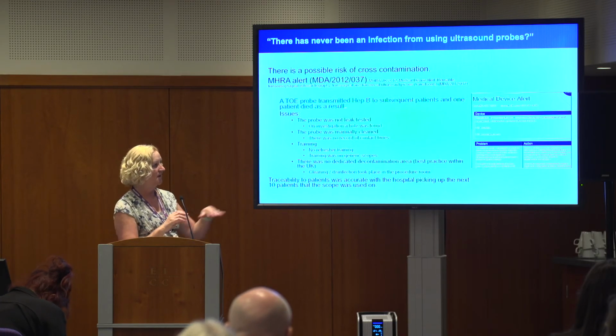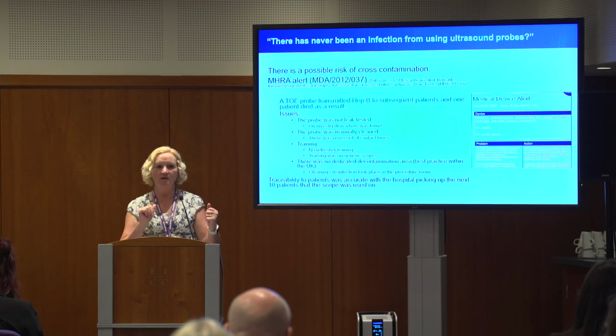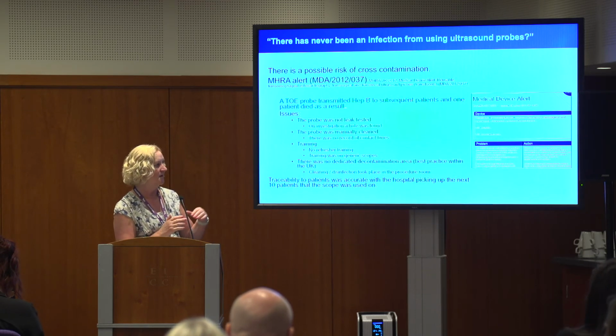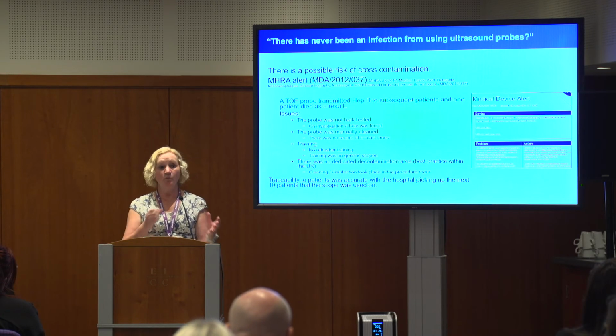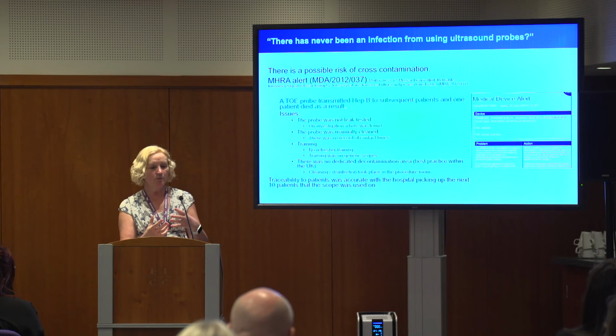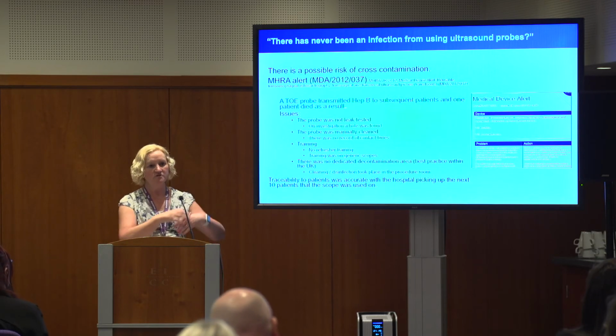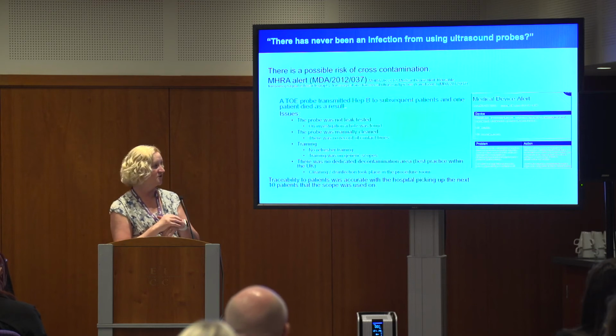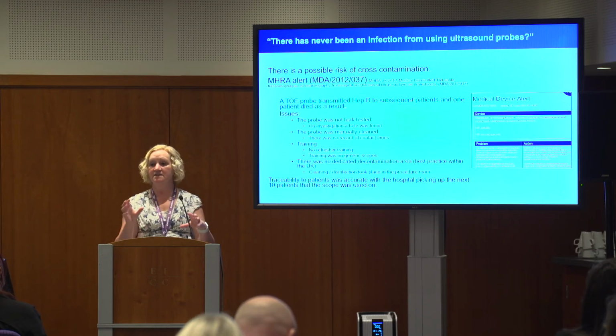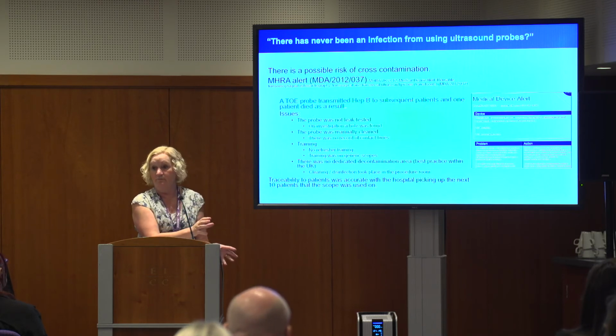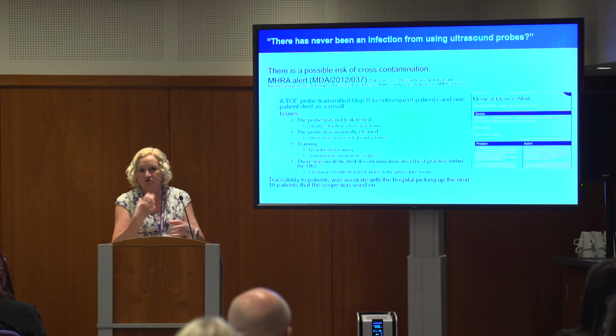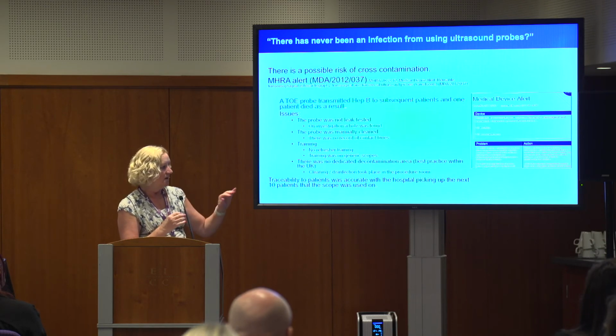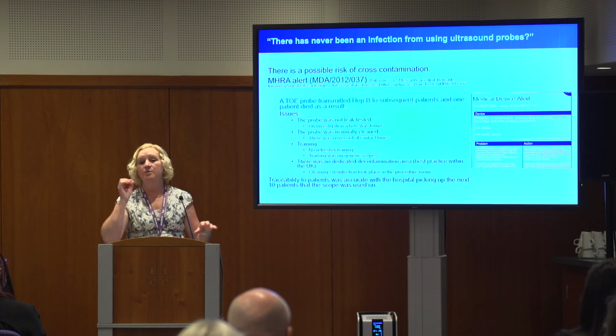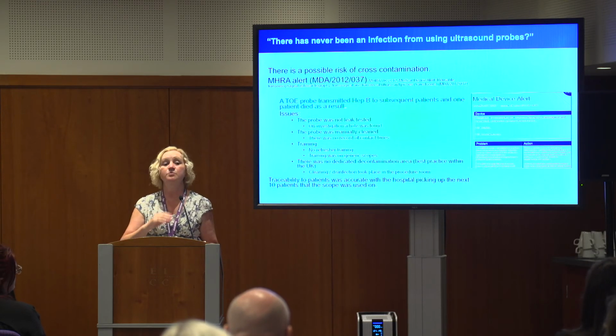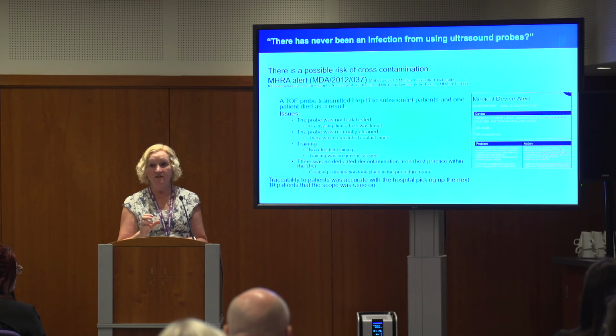There was training, everybody had been trained, but it was a few years ago and there was no refresher training. The training was done on generic scopes, it wasn't done on individual scopes. So the TOE probe, they'd got 2 different manufacturers, training had taken place on one manufacturer, not on the other manufacturer. There was no dedicated decon area, it was shoved in the corner of the room and they did their decon there. So they were trying to get it, pressure of work, to get it through. They had good traceability, so they were able to trace the subsequent patients, which is why the MDA issued the alert, because they knew that it had come from that probe and it had killed somebody.